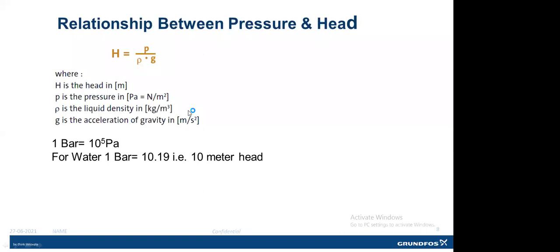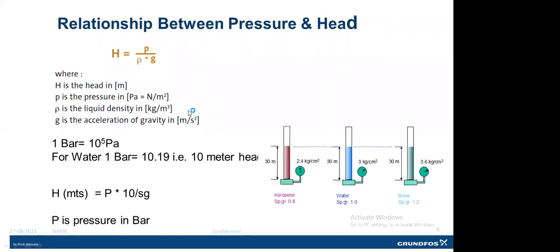Again, if we are not using water, if we are using the pump for another liquid, then how do we correlate the pressure and head? There is another formula. Head in meters corresponds to actual pressure in bar multiplied by 10 divided by specific gravity. So here we can see 3 examples: one with kerosene, water, and brine. Since water specific gravity is 1, a pressure of 3 kg per cm square, or 3 bar, corresponds to 3 into 10, 30 meters of head.